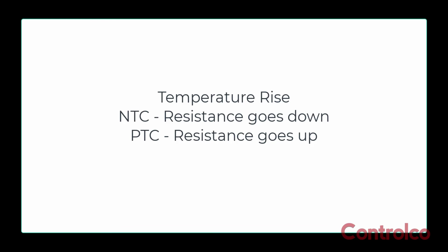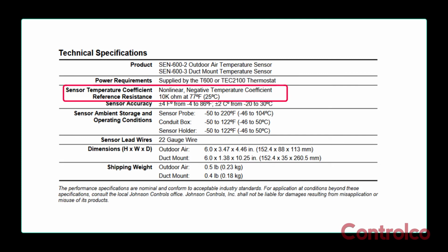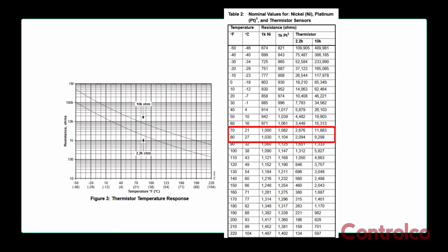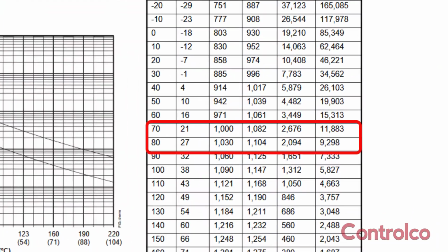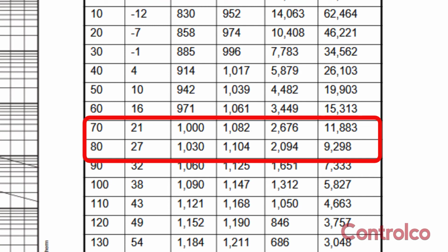So now I have these ohm readings that I got from my meter. How do I make sense of them? First of all, I need to know what my sensor is rated for. I'm using a Johnson Controls temperature sensor. It's a 10,000 ohm type 2 thermistor, NTC. So in the spec sheet, I have a little chart. You can see that here on the screen. The resolution that they give me for the ohms and the temperature chart here, I can't really find exactly what I'm looking at.